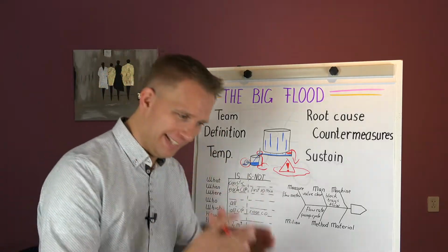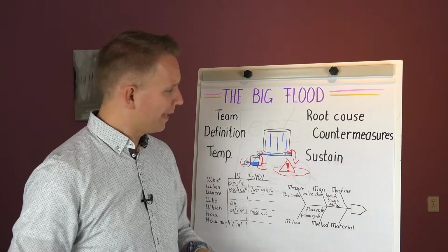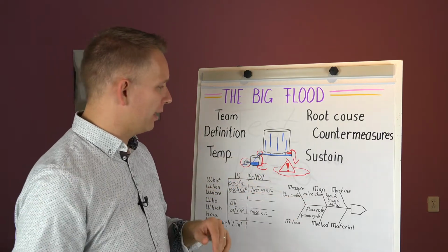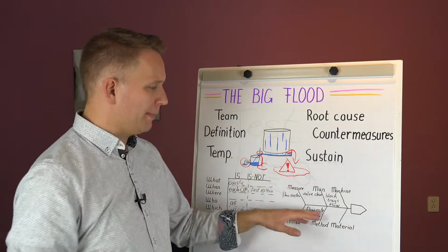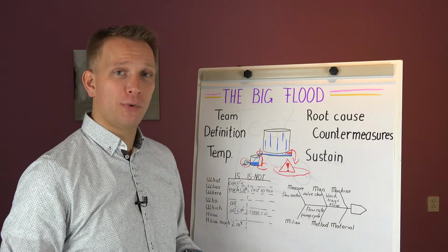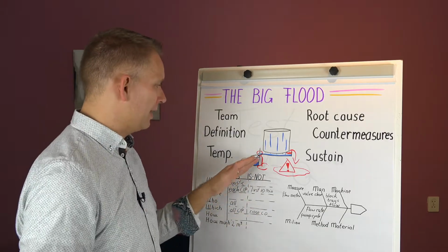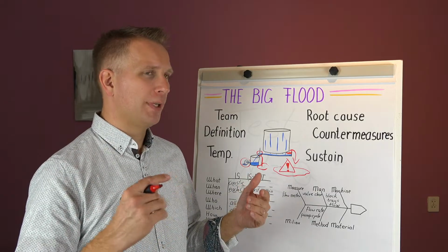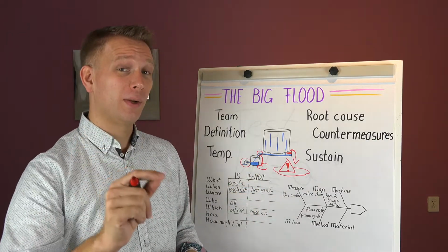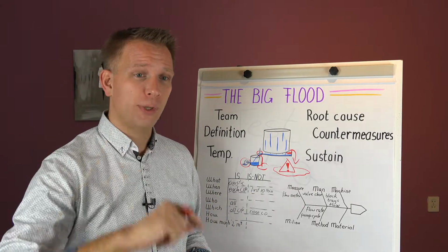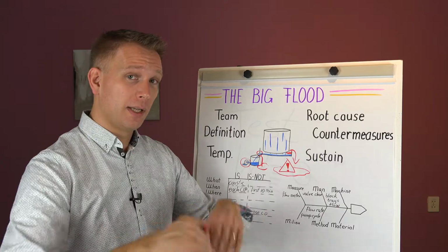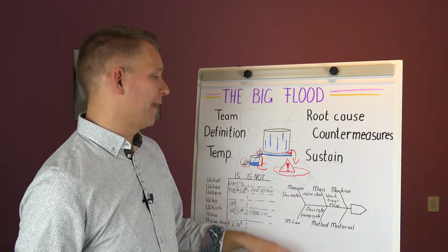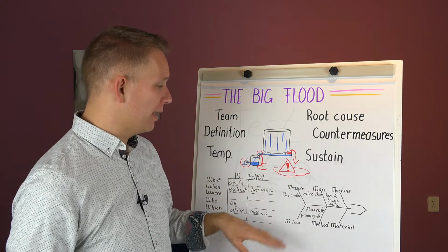We knew that we had the problem defined quite well, but something just wasn't right. So are these pipes blocking? Are the flow rates maybe not good? So we checked the incoming flow rate, which was basically the same as the outgoing flow rate in the beginning, but then the outgoing flow rate dropped. So there was already a problem. Now we knew that the flow rate of the cleaning liquid was increased 2 years ago, so that's one of the temporary controls we also did. We put it back down and made a slightly longer cleaning. It didn't help a lot though, but it did prevent at least this spillage.